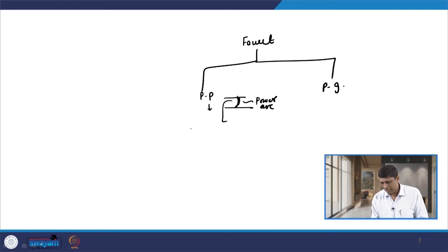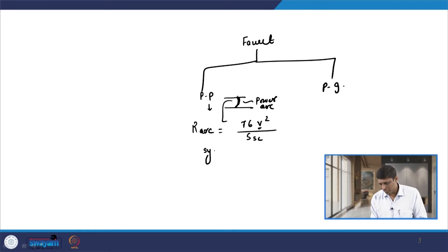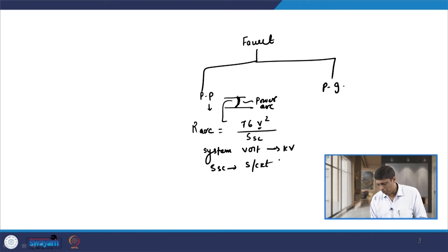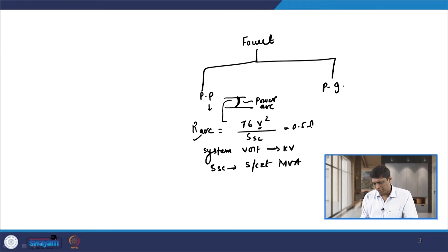When a power arc is present, the value of arc resistance can be obtained with an empirical formula: 76 V² / SSC, where V is the system voltage in kV and SSC is the short circuit fault MVA at the location of the fault. Using that, you can determine the arc resistance, and it usually comes out to be approximately 0.521 ohm, so this is fixed.